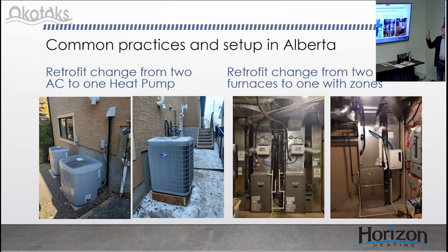And because all this equipment is variable speed, if the top floor calls for cooling and just needs a little bit of cooling, then everything comes on with the right airflow and right cooling just for that zone. If it gets warmer out and the top floor needs more cooling, the system will ramp up to meet that demand. Then if the main floor calls for cooling, the dampers will open accordingly, and the system can choose to speed up or not, depending on if it needs to, but most likely it would increase the airflow to meet that other zone. And then with heating, you could heat the main floor and not heat the top floor as well.